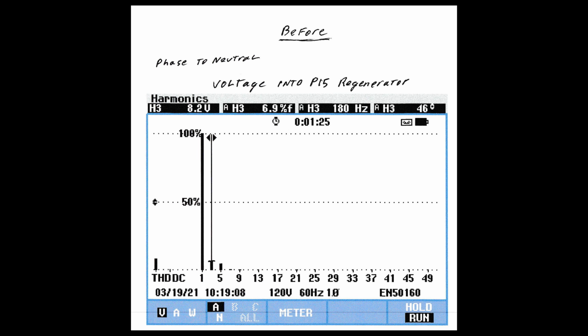Here we have a screen capture of the Fluke meter on the input going to the P15 regenerator. Just to explain this real quick, you have your total harmonic distortion, which is a little short line on the far left lower corner of the graph. Your 0 to 100% line right over the number 1 is your first order. That would be your line voltage of 120 volts. And every order thereafter is a harmonic that's not part, or really shouldn't be part, of the 120 volt sine wave. So you'll notice the small thin line between the 1 and the 5, which is a third order harmonic. We'll highlight those peaks in the next slide and explain it a little further.